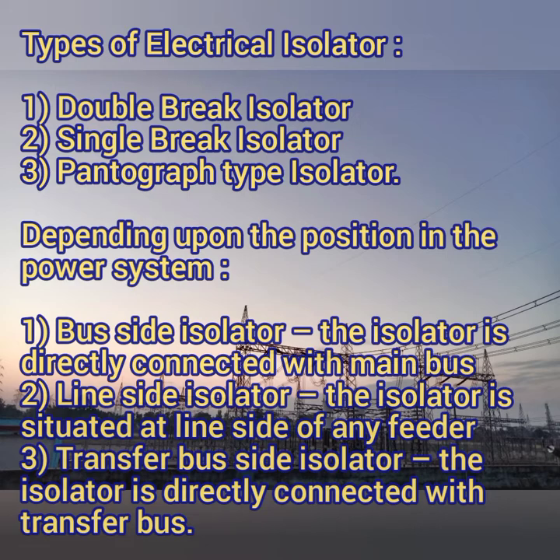Depending upon position, isolators are classified into three types: bus side isolator, line side isolator, and transfer bus side isolator. The bus side isolator is connected very near to the main bus. The line side isolator is situated on the line side, away from the bus, where the line connects to another station. The transfer bus side isolator is used in systems with a two-bus or single-bus-with-transfer-bus arrangement. In case of a main bus failure, the bypass isolator on the transfer bus side gets closed, keeping the line healthy.